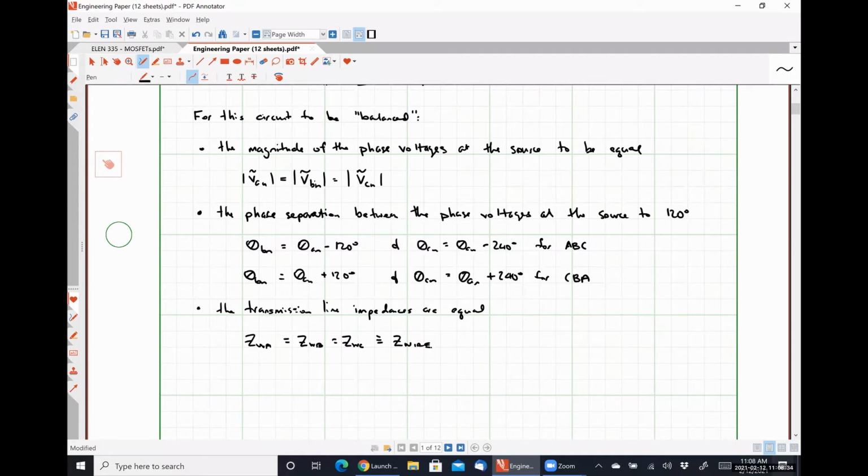If your system is unbalanced, the neutral conductor only carries the unbalanced portion, which is typically much, much smaller than the other conductors. So ZWN does not need to be equal, is the only point I'm trying to make here. We'll mathematically prove it momentarily.